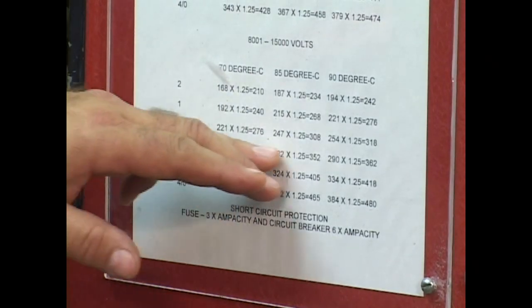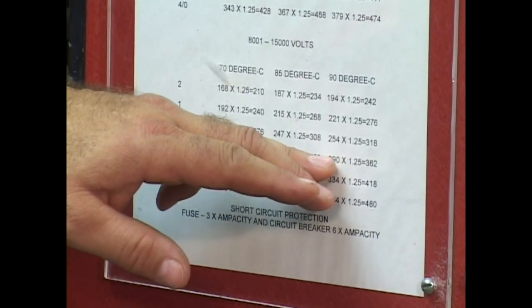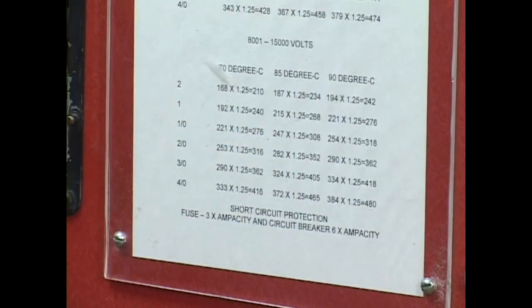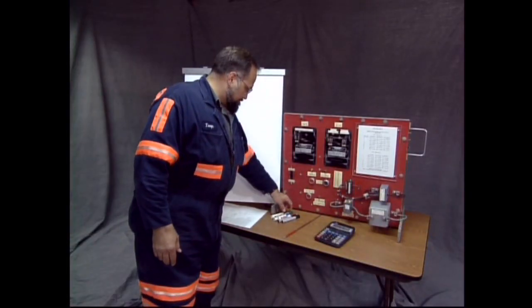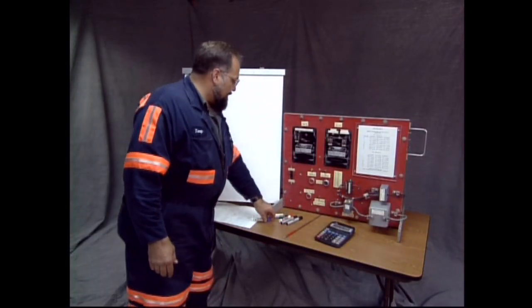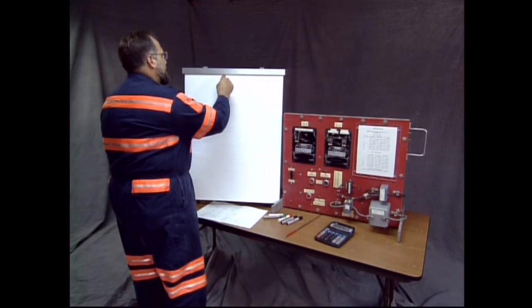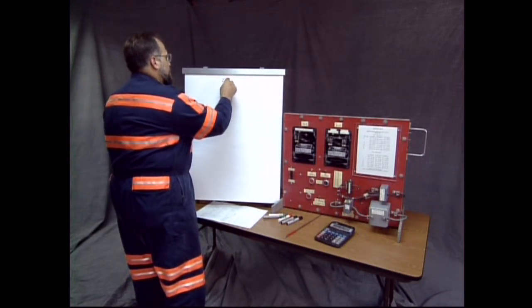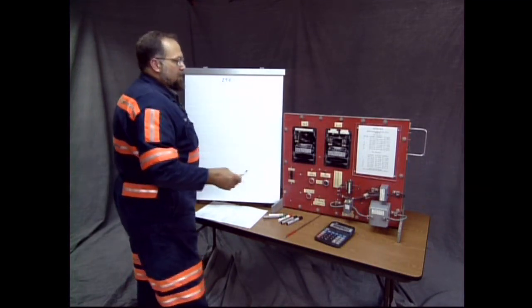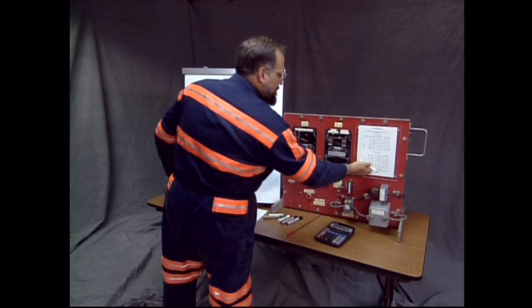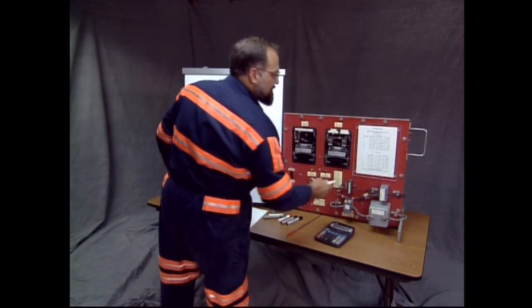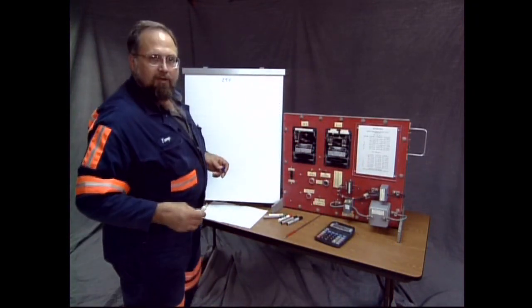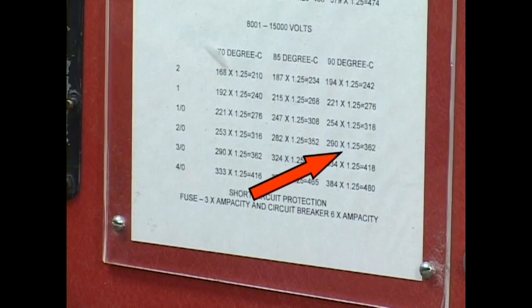2 aught, 90 degrees C. It says the ampacity is 290. That's an important number. So let's make a note of that. 290 is the ampacity. Now, it's already calculated for the overcurrent setting. It's 125% of the ampacity. That's times 1.25, which in this case would be 362.